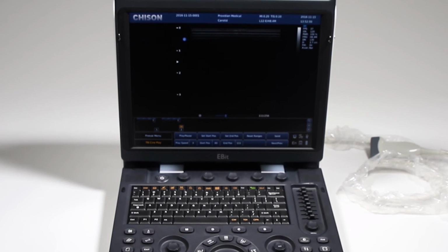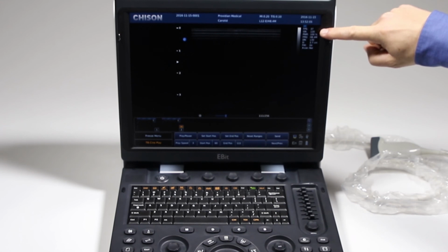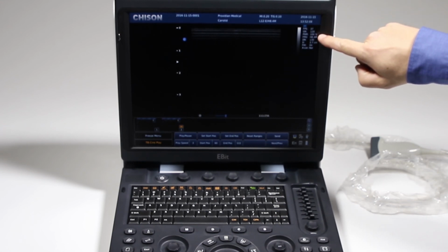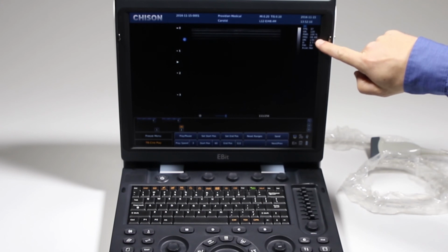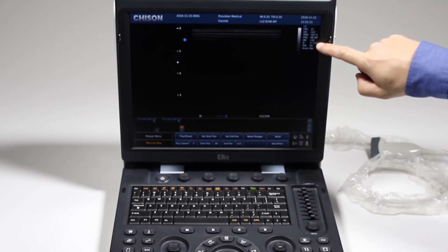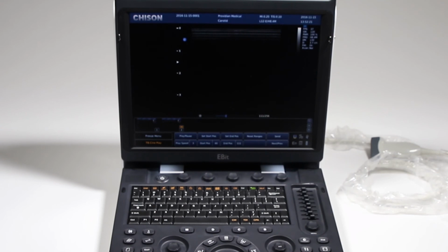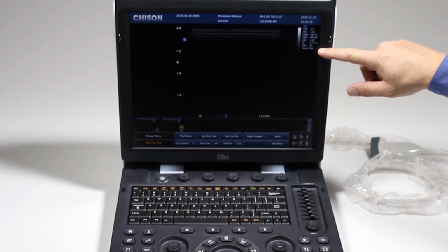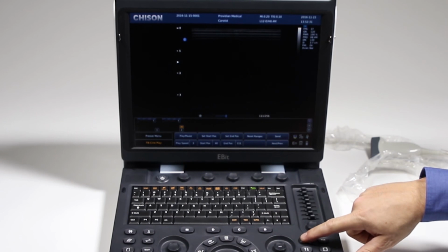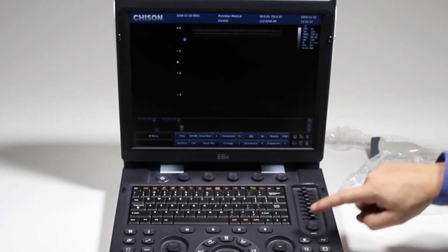And now down along the right hand side, you have FPS, which stands for frames per second, your gain level, the acoustic power, which we saw in that utility menu, the current frequency for imaging, your dynamic range here, the depth. So this says 3.7, so along here these markers show that my depth is down to 3.7 at the very bottom of the image. FHI is for the harmonics imaging. X contrast, which we showed here, you have normal, and if I unfreeze, you have normal, enhance, superficial.